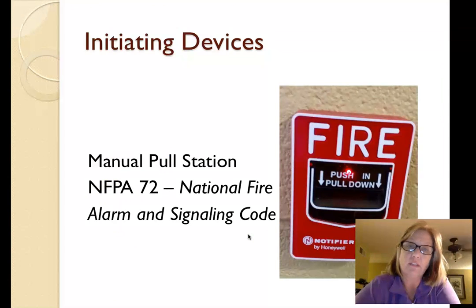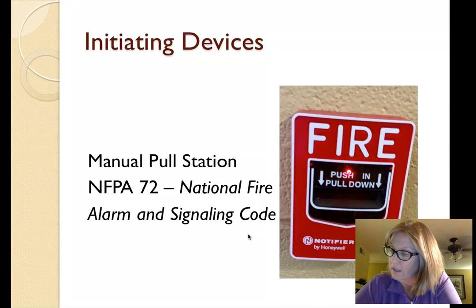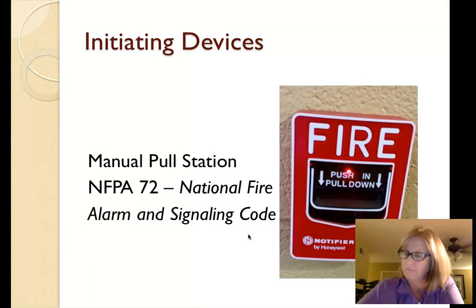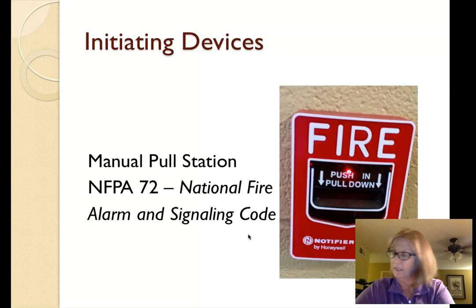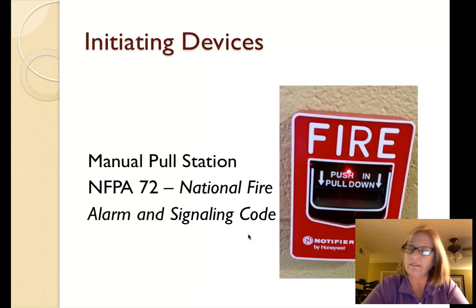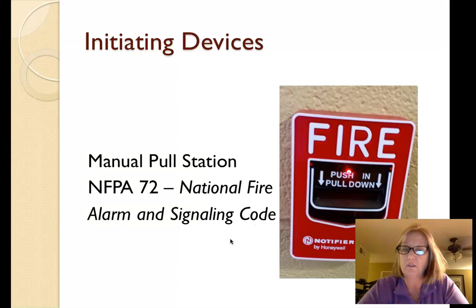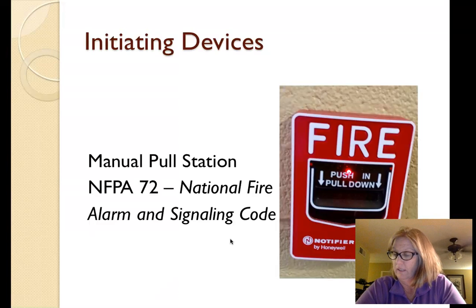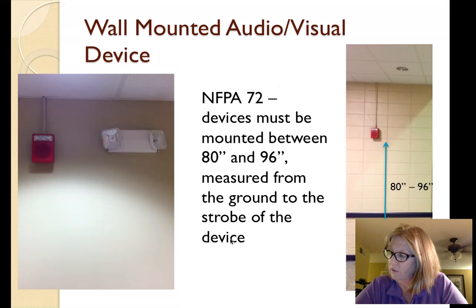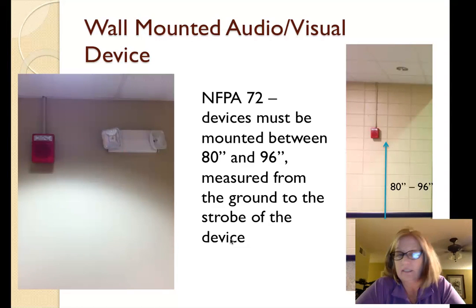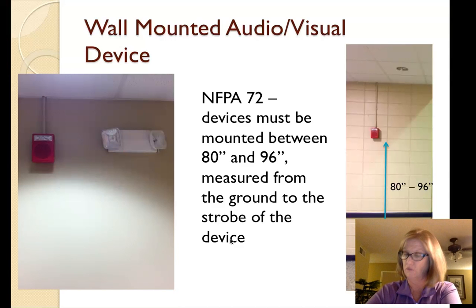Within that kitchen also there was another strobe light notification device near the hood system. There were manual pull stations by the elevator and by all of the exits per the NFPA 72. By this code, pull stations must be 5 feet from an exit door and have to be 42 to 48 inches from the floor to the activation handle. Also, this code shows a wall-mounted audio-visual device has to be between 80 inches and 96 inches, measured from the ground to the strobe device, as you can see here on the right.